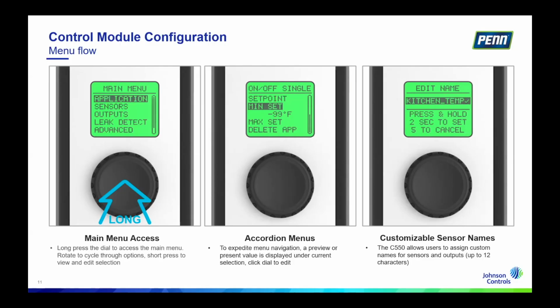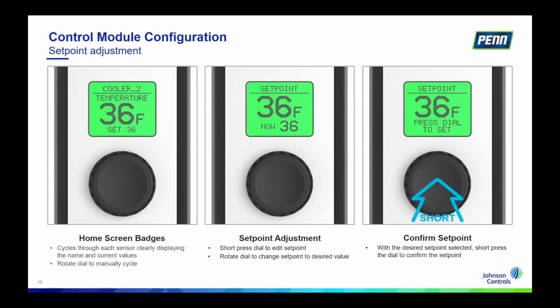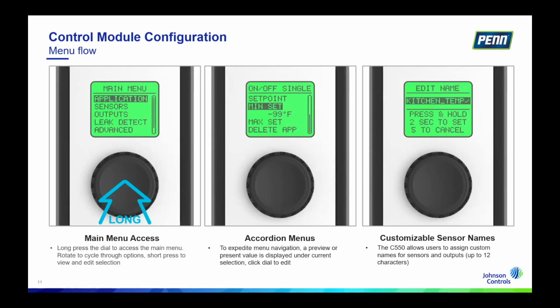So the applications allow you to quickly get a subset of configuration points so that you can easily configure the device. Now, one of the things you'll see here is that if you go back a minute, you can have several applications actually running on a single C550 controller. And as I mentioned earlier, the leak detect functionality actually sits on top of any other application that you're going to set. So that we meet the requirements of UL 60335, where any of your outputs are going to be overridden as part of that leak detection menu.